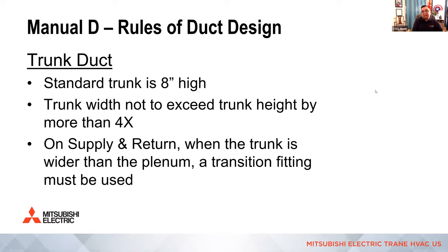On a supply and return, when the trunk is wider than the plenum, you have to use a transition fitting. I don't have a picture of this in this particular presentation, but I have some in other ones. This happens a lot when you have a system replacement in a vertical application and they add, let's say, a cabinet air filter right next to it. Now this pushes the return drop out compared to what was there, and it may not line up with your typical return trunk running down that basement. If you don't use a transition fitting to get back there, you're going to block not the full size by just stabbing it into the corner of it. So anytime the trunk is wider than the plenum, you have to use a transition fitting. You can't just stab it into the side of it like I was talking about before.